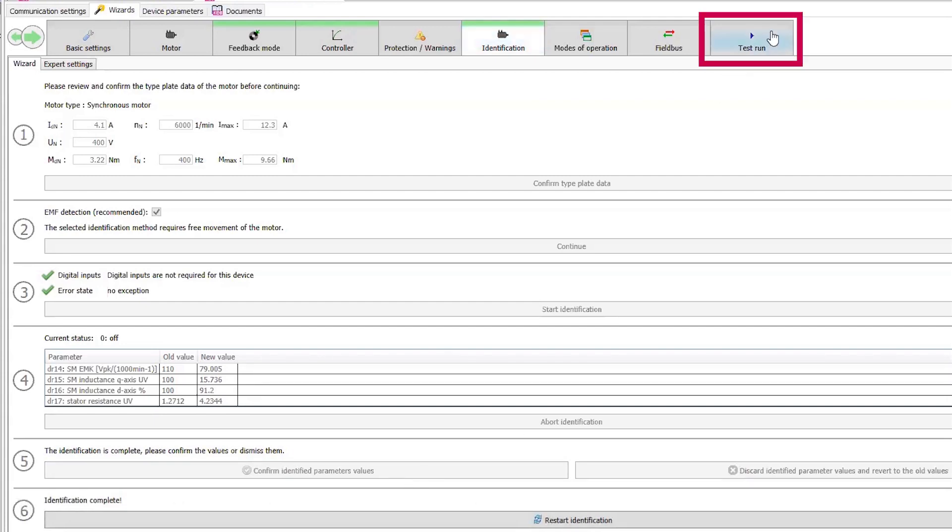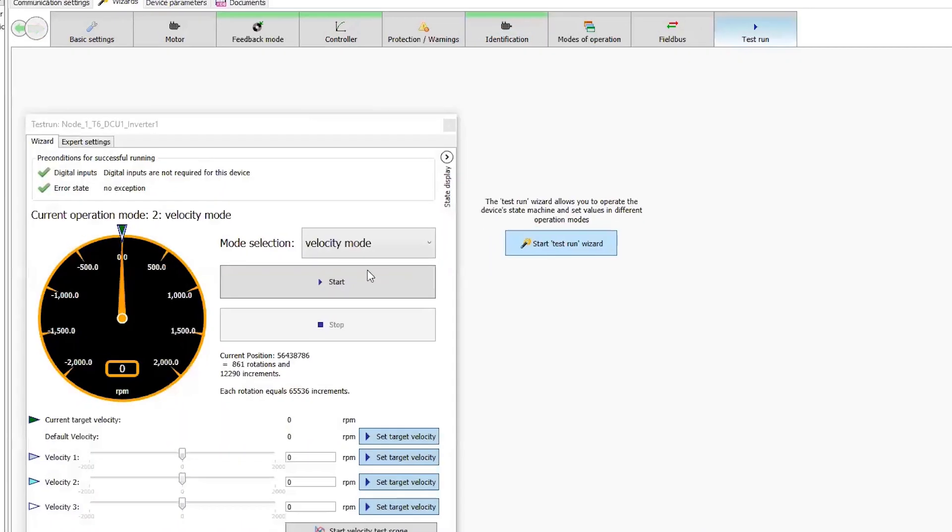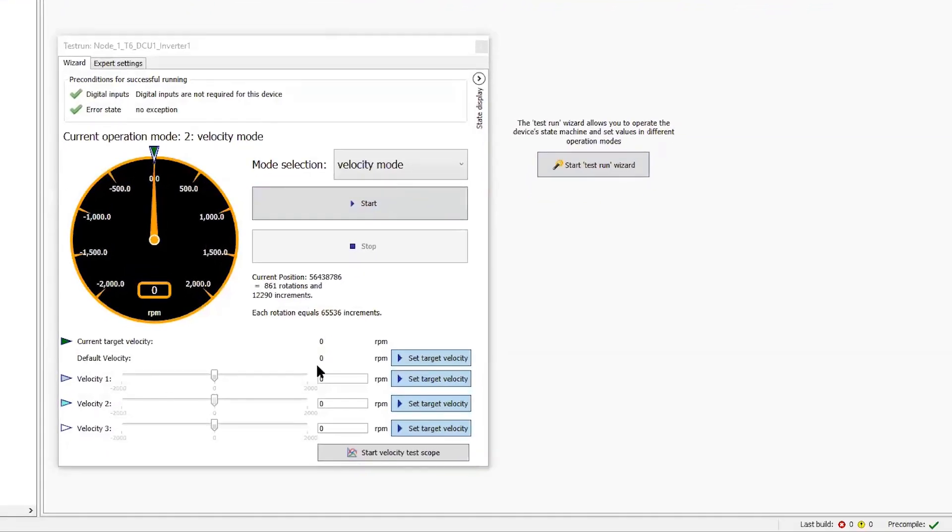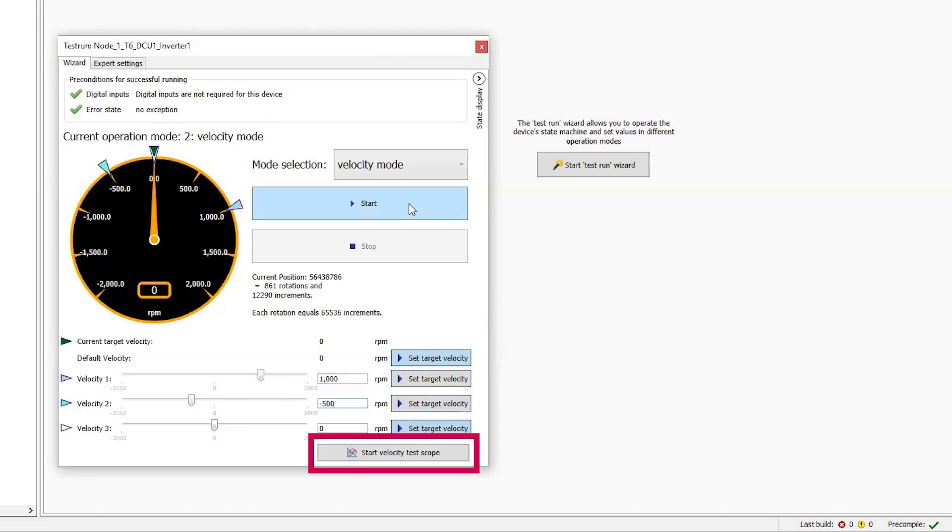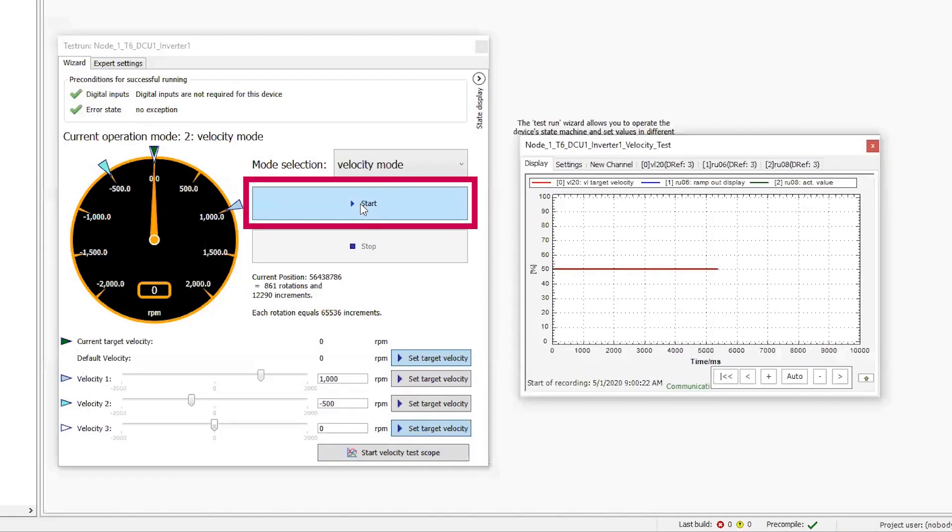Next, I can go to the test run tab, start the test wizard, enter in some values for speeds, so 1000 RPM, negative 500 RPM. I can also select a pre-configured scope trace, which shows the command speed and the actual speed. Then I'll give it the start command and a hardware enable.